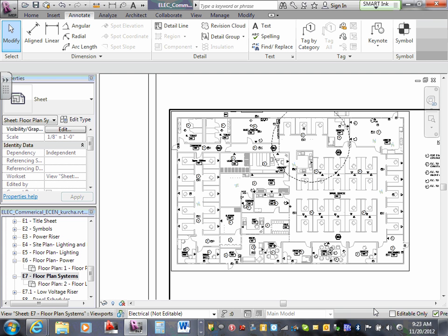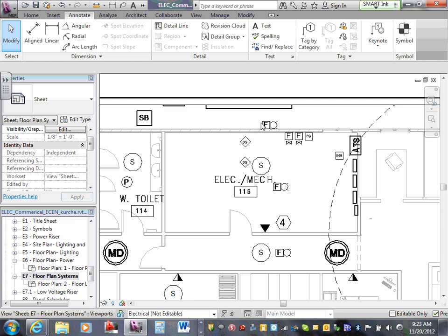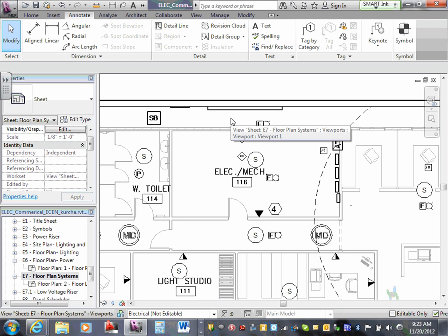The indicating circuits, obviously with the strobes, are your main draw for power. So when you're sizing batteries, that's what you need to consider. But smoke detectors, when you're sizing those circuits, the draw is so little, all it's doing is sending a signal. And Joe, don't they send 120 to the duct smoke detectors? I thought they powered them. Yeah, that usually needs a 120 volt circuit just to power it, and an initiating circuit to it.